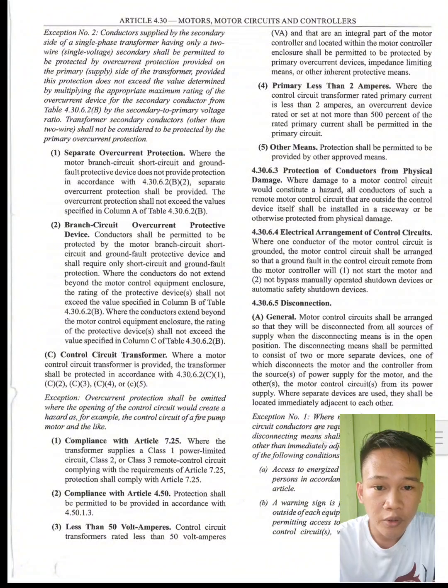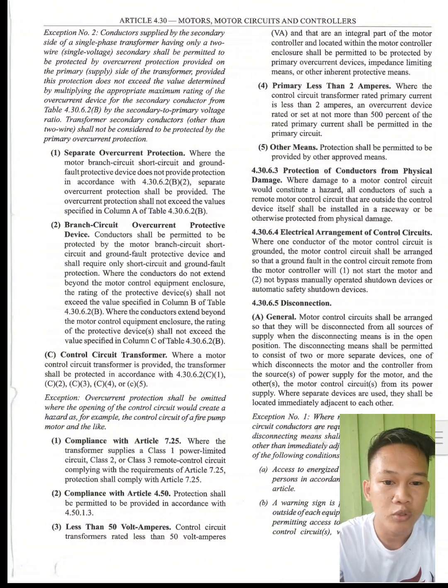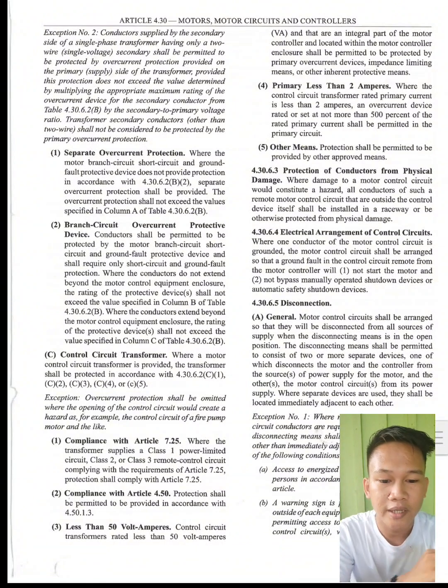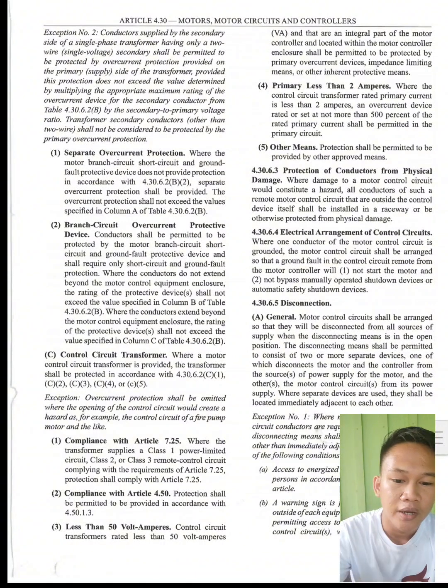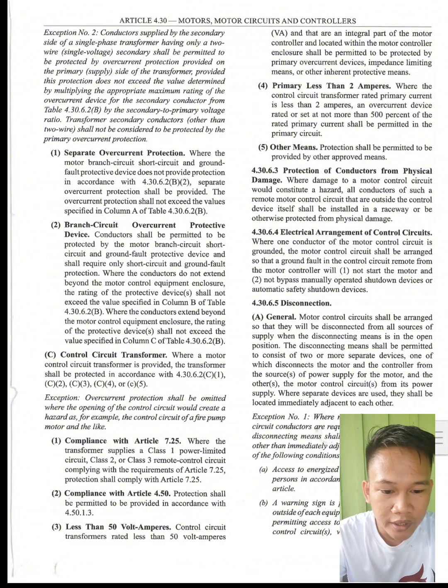First, we have separate overcurrent protection, where the motor branch circuit, short circuit, and ground fault protective device does not provide protection in accordance with 4.30.6.2 B2. Separate overcurrent protection shall be provided. The overcurrent protection shall not exceed the values specified in column A of table 4.30.6.2b. Second, we have branch circuit overcurrent protective device. Conductors shall be permitted to be protected by the motor branch circuit, short circuit, and ground fault protective device, and shall require only short circuit and ground fault protection.